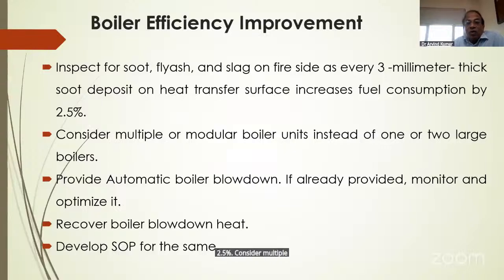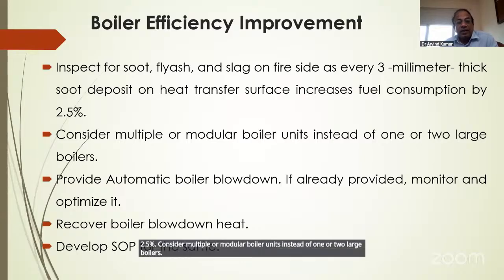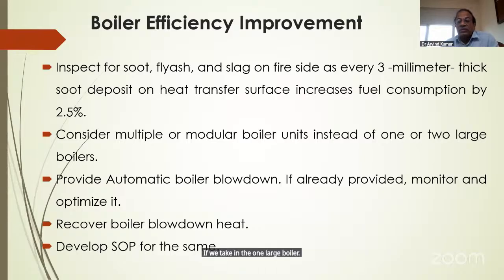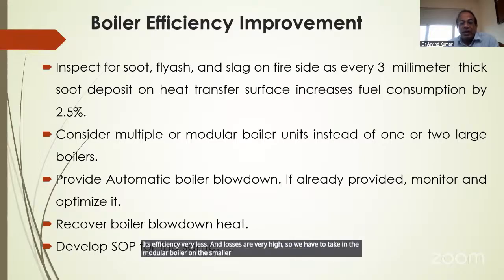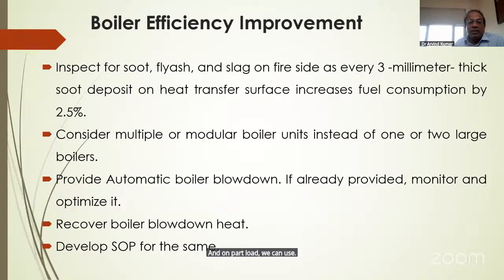Consider multiple or modular boiler units instead of one or two large boilers. If we take one large boiler, then at part load its efficiency is very low and losses are very high. So we take modular boilers of smaller size, and on part load we can use them as per the need. Provide automatic boiler blowdowns, and if already provided, monitor and optimize them. Recover boiler blowdown heat. Develop a standard operating procedure for the boiler, so that every time things happen with the proper protocol, and feedback is taken in time and recorded.